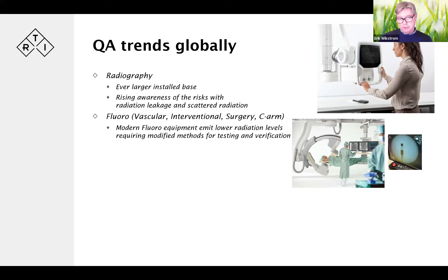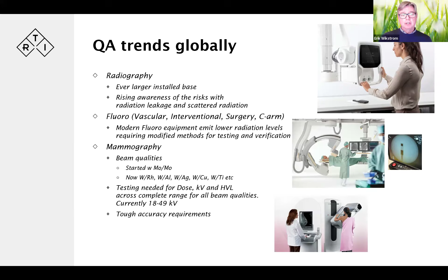Mammography is also growing, especially in developing countries, where we also see the beam qualities across the usage. It started with moly, but now we see all kinds of different target filter combinations that we need to keep track of and monitor in a good way. And the range is now growing into the high energies, up to 49 kV, and we need to monitor that across the whole range. So there are some tough accuracy requirements, especially in mammography, because those tolerances are getting tighter. So we need to know how we can cut those corners.